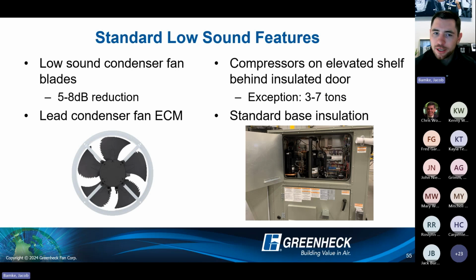Sound. So I mentioned 50% of our equipment about goes to education. So obviously when we have schools and neighboring residences next to playgrounds, whatever it may be, sound's usually an issue. And so we standardize on some components like the low sound condenser fan. That is a standard condenser fan. You don't need an acoustical package of any sorts. And we include a lead condenser fan, ECM, as standard as well. So that really reduces your overall sound, especially at part load conditions.